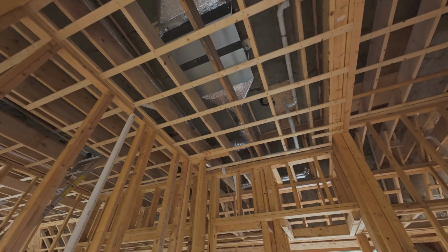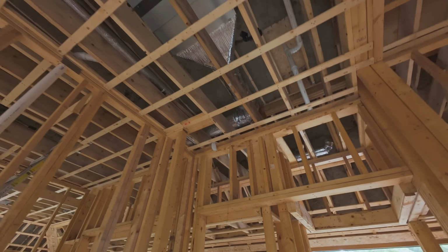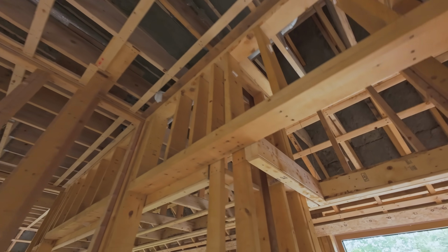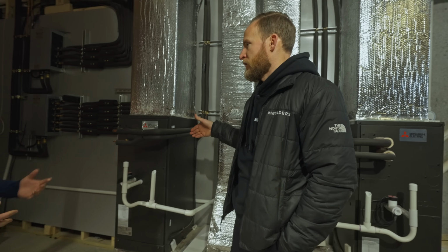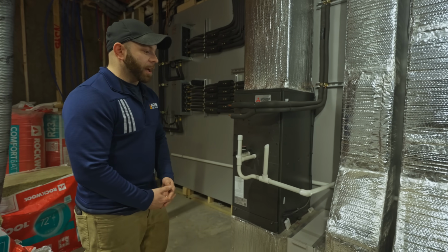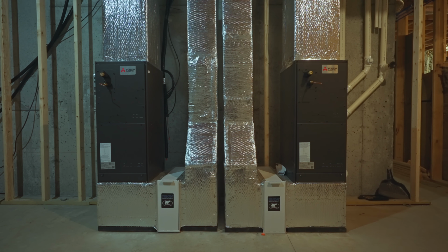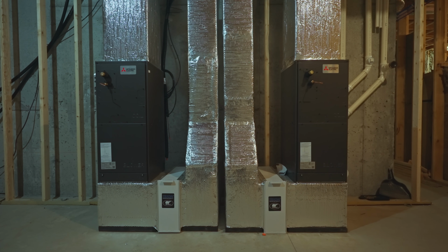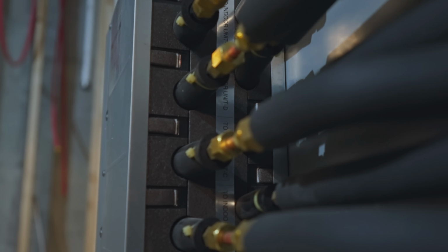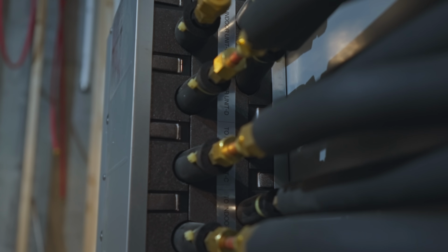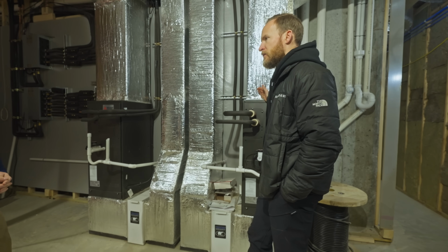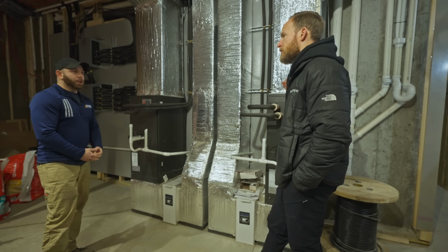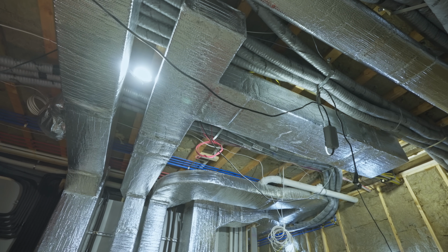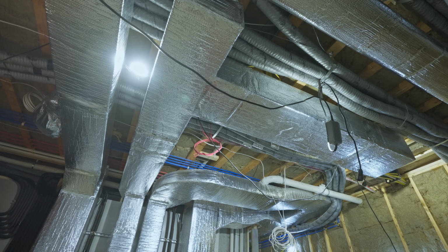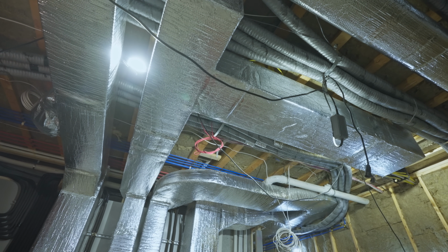So you're talking about the units up in the second floor ceiling. We have a couple down in the basement, but these are not pancake units, right? No, these are actually the SVZ high static air handlers. They're just like a regular conventional air handler, just mini split, and we can connect them right to our branch box too. What does high static mean? It just means more airflow, so we can get more duct run out of them. So you can really push air a lot further in the home. Yes.